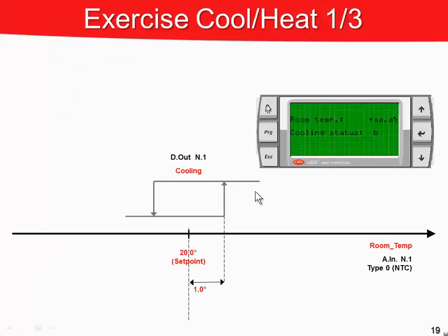These are the requirement specifications of the first exercise. There are only two operating parameters, that is the set point and differential. The set point defines the central value of the stage, while the differential defines the half of the stage.